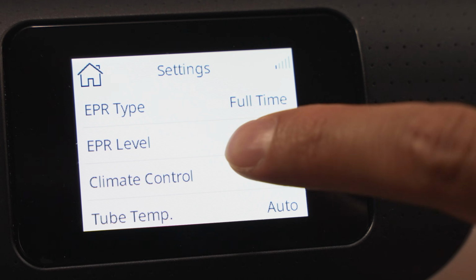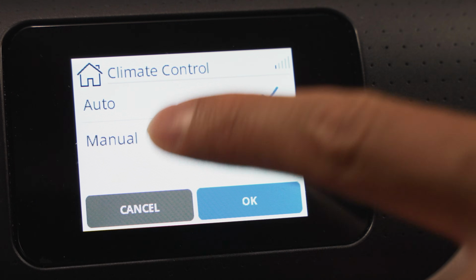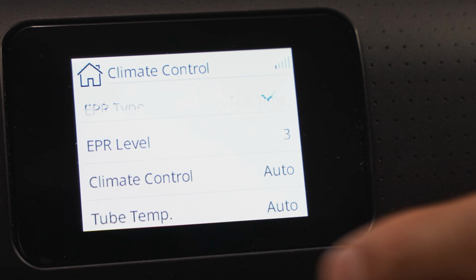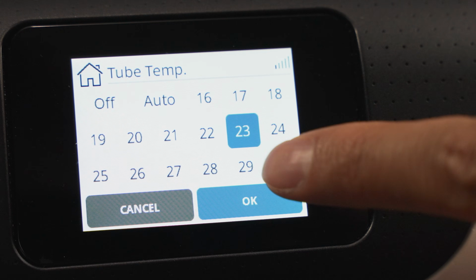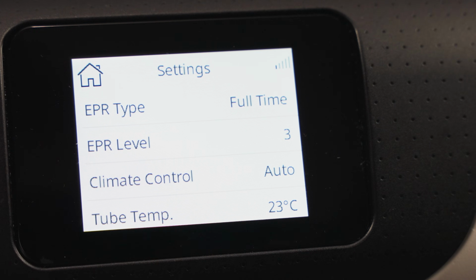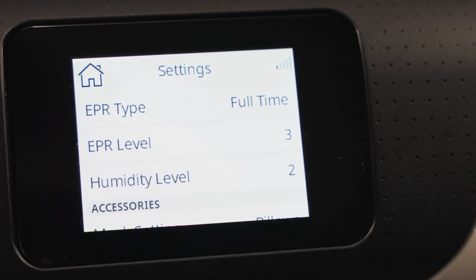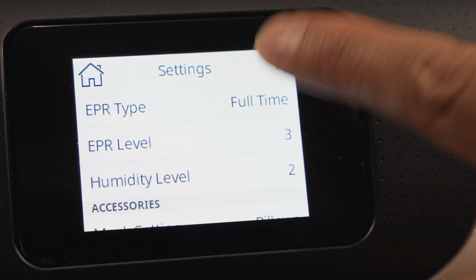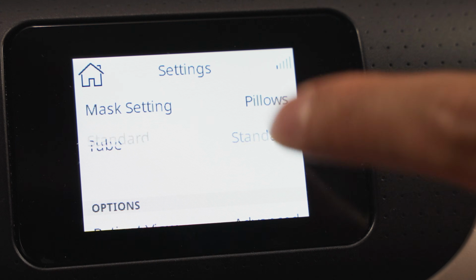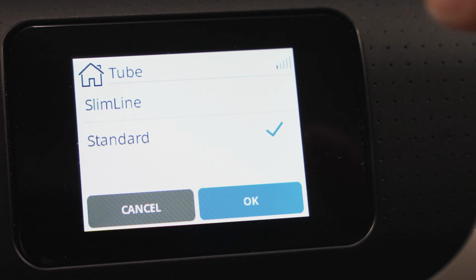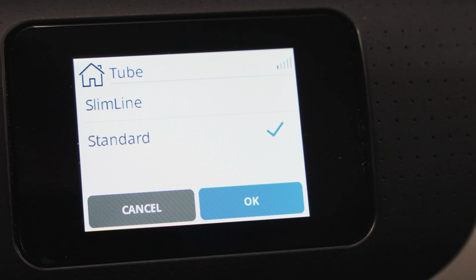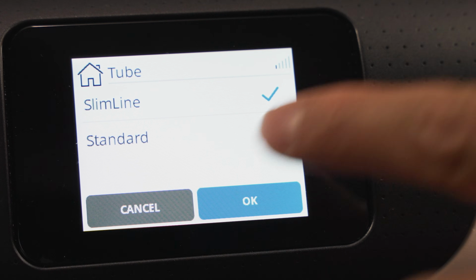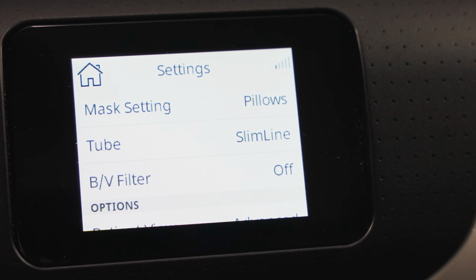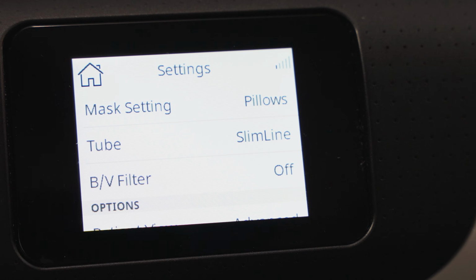Okay, we have climate control here. It has auto, manual, auto mode, okay. We have tube temperature, you can do it off, auto, or whatever temperature you like. If I disconnect the climate air out of the back, then it disappears, and we're gonna see our tube just goes from standard to slimline. So standard is a thicker tube, 22 millimeters. Slimline is a slimmer tube, okay? Most people nowadays are buying and using slimline tubes.